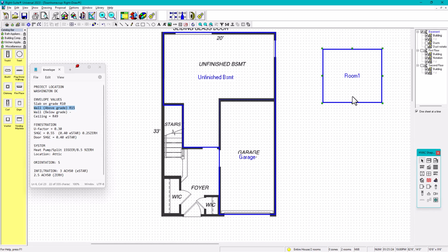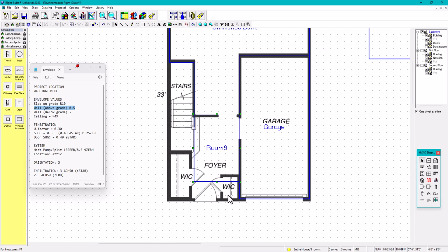Now what we're gonna draw is the foyer. The foyer is going to be right here, and then we're going to make it again. It's kind of my method. Now, you might be wondering, Roberto, are we going to draw the walk-in closet small and the walk-in closet big? And the answer is not really, unless you think that the walk-in closet will be conditioned with a separate outlet with a separate register. Usually when the walk-in closet is big, and you're gonna condition that, you're gonna put a register, yes. But in this case, since they're small, we are not going to draw them. We don't need the CFM. We're just gonna draw it overall.